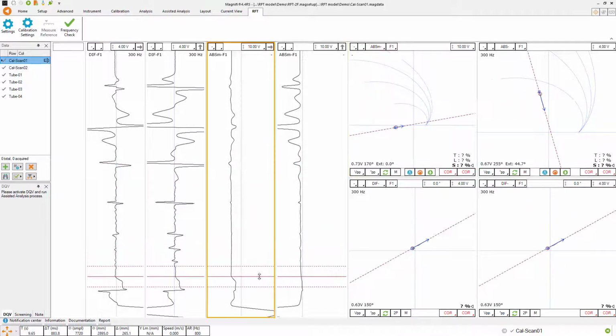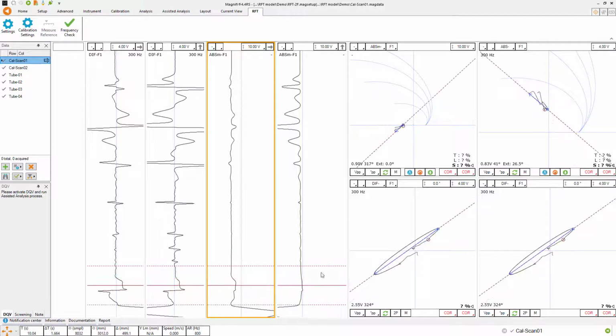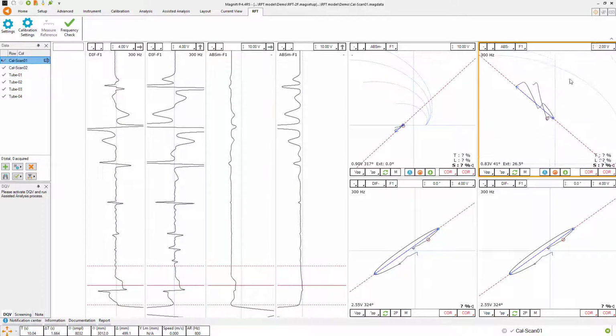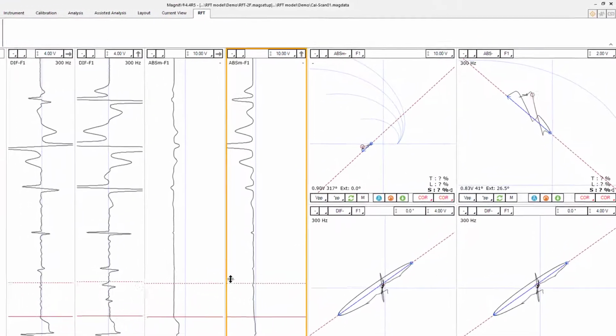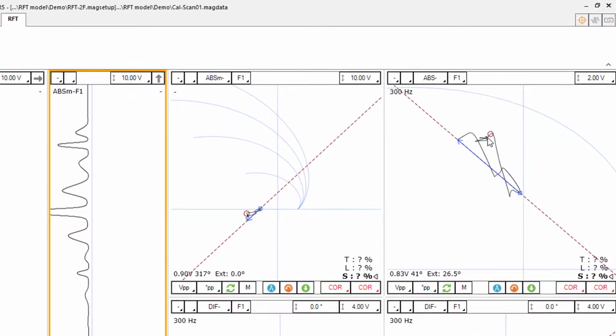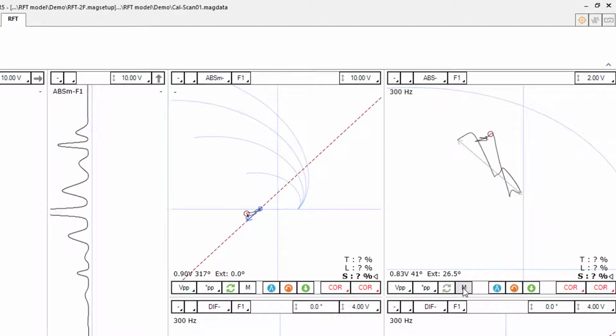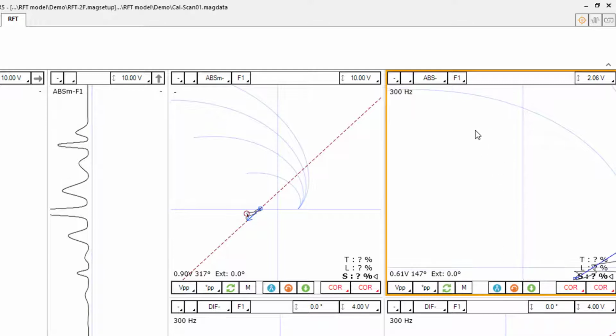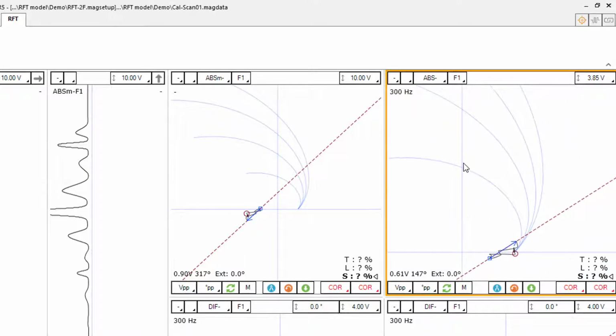With the old system we had to select the support plate at the end here, and typically people were looking at the support plate signal, trying to locate the nominal point right here, accessing the manual measurement mode, and tracing a vector from the nominal parallel to the main orientation of the support plate, and then doubling the signal to provide the expected 0 point at the end of the arrow here. By doing this and normalizing, it was bringing the signal correctly in the voltage plane.